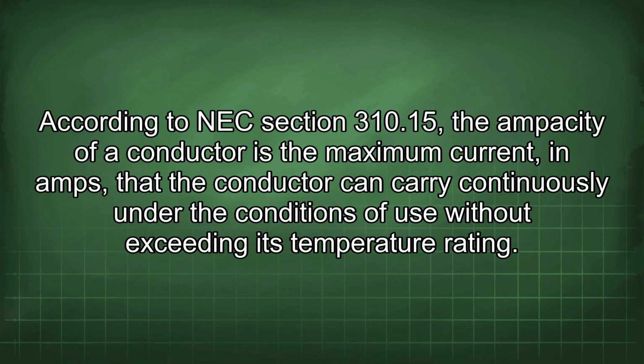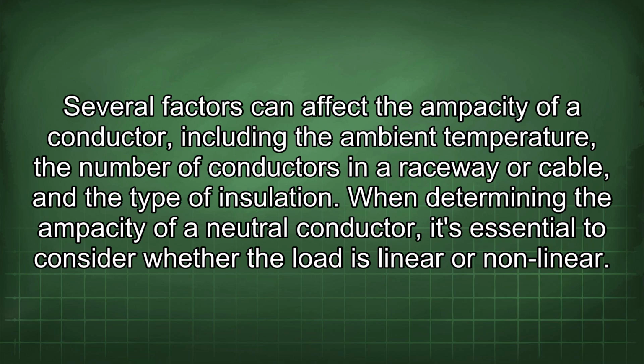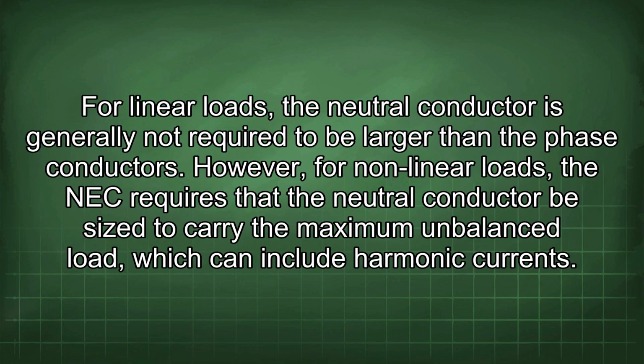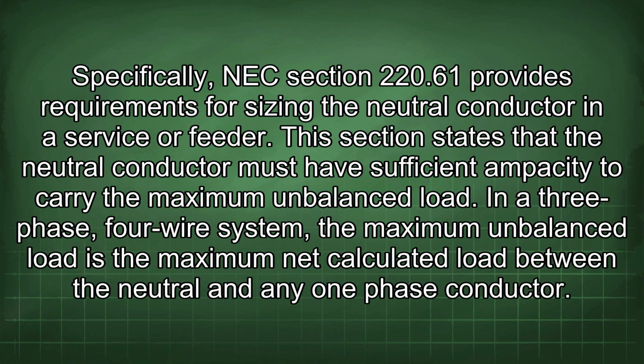According to NEC section 310.15, the ampacity of a conductor is the maximum current, in amps, that the conductor can carry continuously under the conditions of use without exceeding its temperature rating. Several factors can affect the ampacity of a conductor, including the ambient temperature, the number of conductors in a raceway or cable, and the type of insulation. When determining the ampacity of a neutral conductor, it's essential to consider whether the load is linear or nonlinear. For linear loads, the neutral conductor is generally not required to be larger than the phase conductors. However, for nonlinear loads, the NEC requires that the neutral conductor be sized to carry the maximum unbalanced load, which can include harmonic currents.